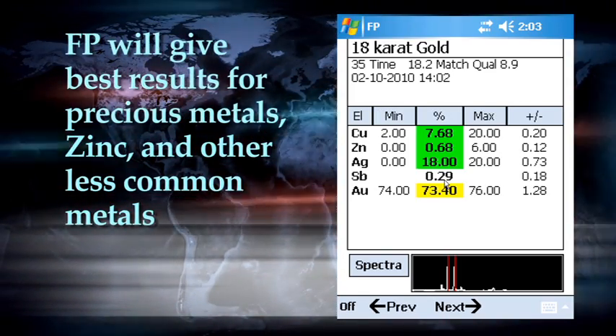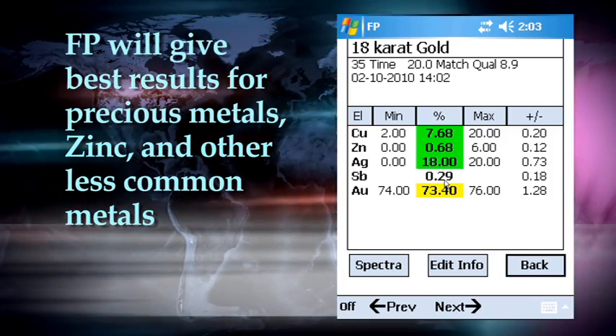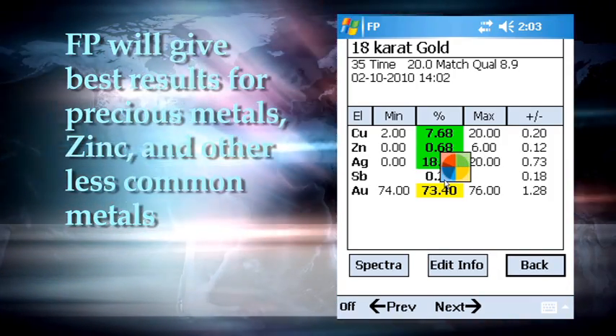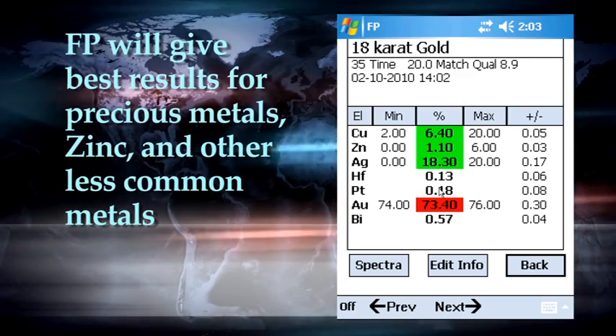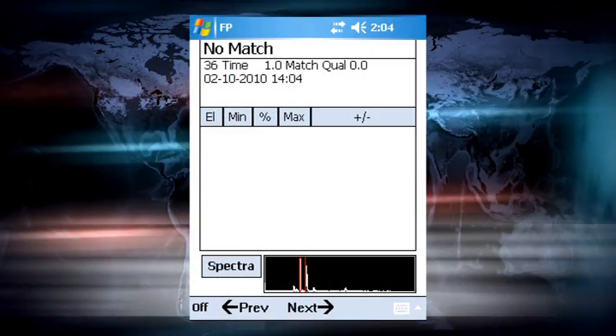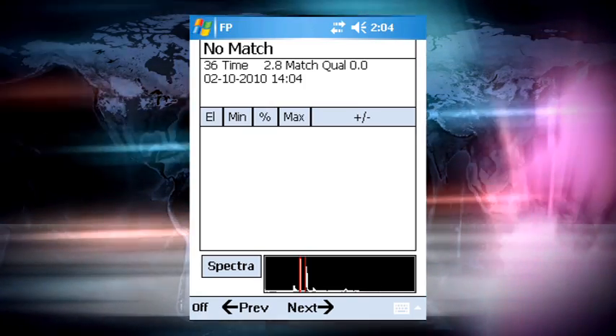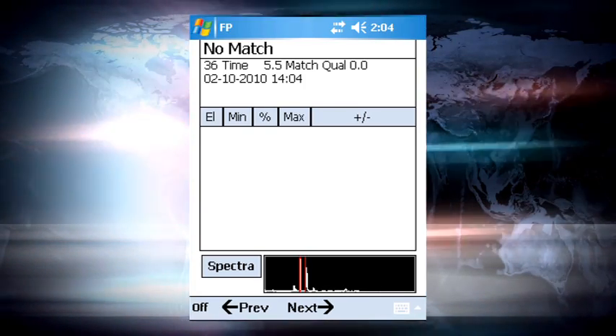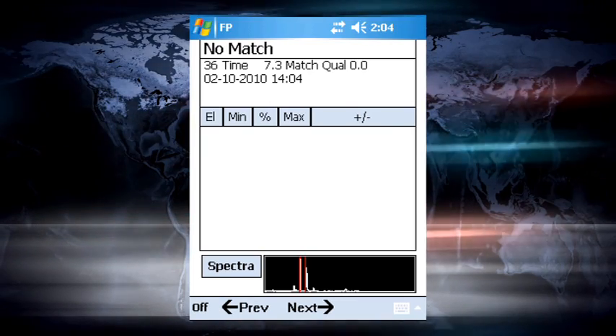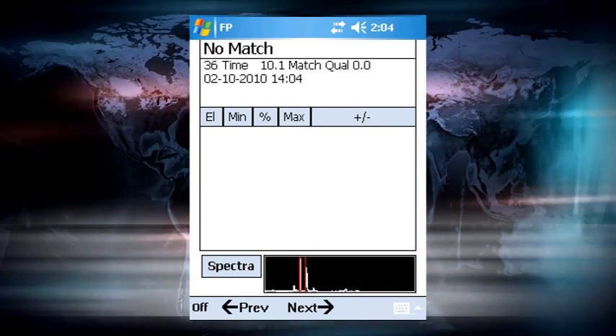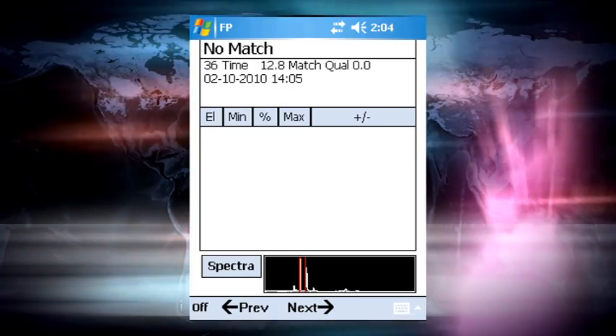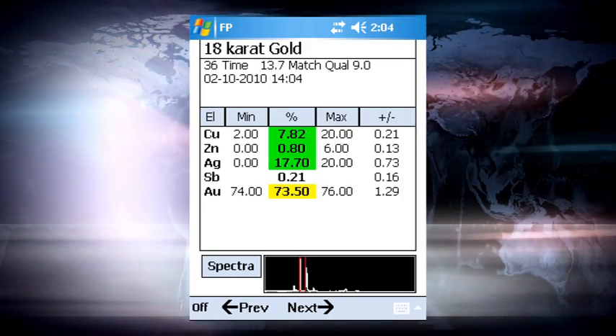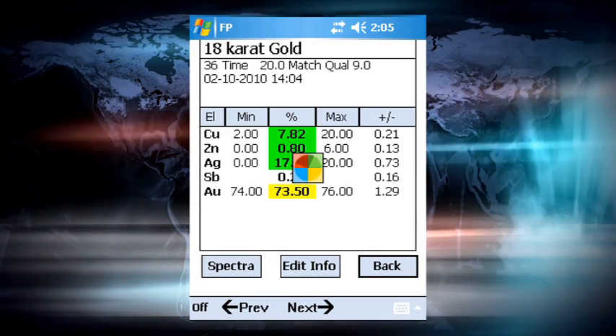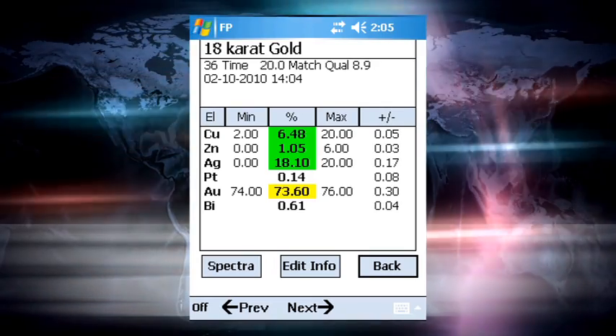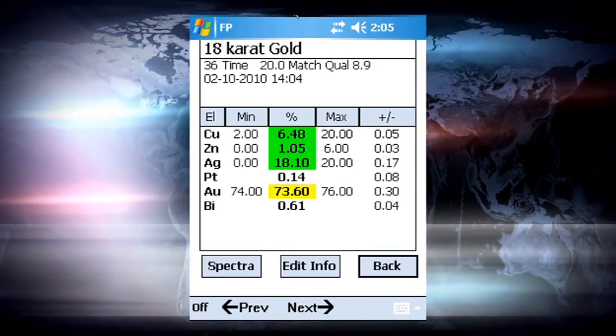For completely unknown samples and alloys such as precious metals, zinc alloys, and other less common metals, fundamental parameters analysis will give the best results. When the fundamental parameters calculation is performed, there can be a substantial delay between the acquisition of the data and the presentation of the results. This is why the first results take some time to appear on the screen, and also why the final results are not displayed immediately. In this case, the spinner icon appears indicating that the analyzer is busy calculating the results. When this happens, simply wait for the completion of the calculations and display of the data.